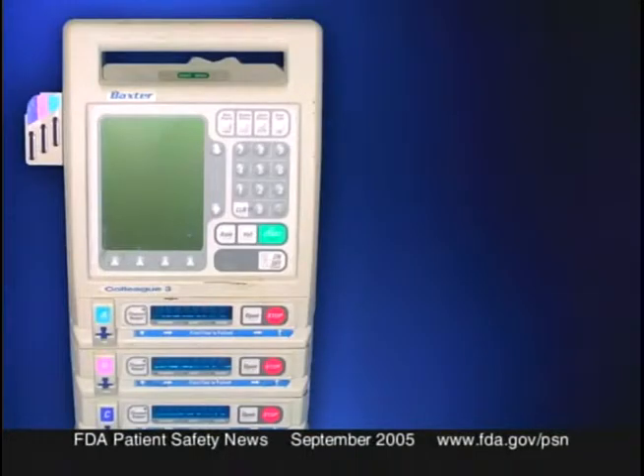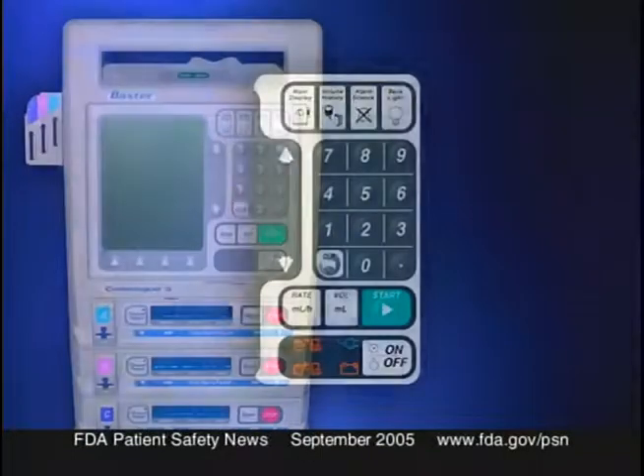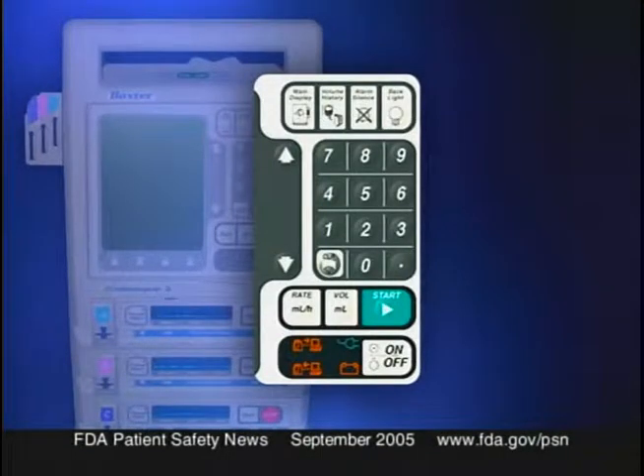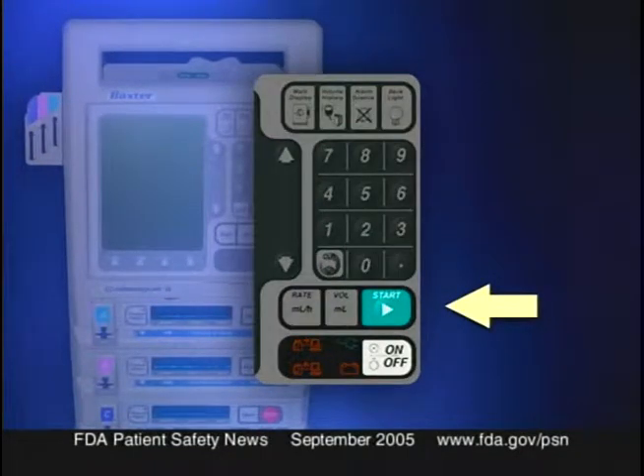These devices may also have two other problems. First, because of the way the pump is designed, it's possible to inadvertently press the on-off key instead of the start key when trying to start an infusion. Also, if the pump is left on while being connected or disconnected from a hospital's monitoring system, the device can fail, so the infusion has to be restarted.